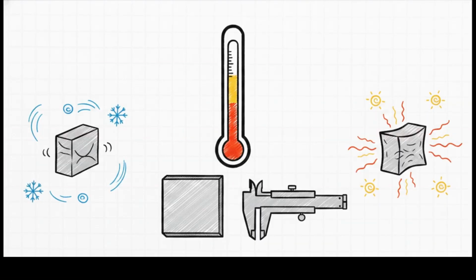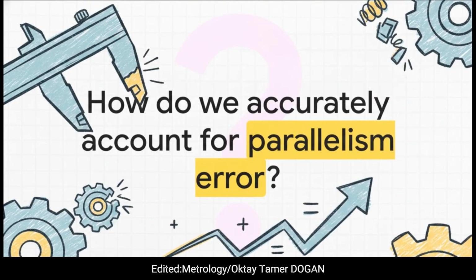Lab environments profoundly impact dimensional calibration. There is a universal consensus that the steel in these devices hits its optimal, most predictable thermal state at exactly 20 degrees Celsius. It's the absolute truth for standards organizations and manufacturers alike. Any deviation from 20 degrees creates quantifiable uncertainty because the material physically expands or contracts. And remember, that thermal error hits both the caliper and those incredibly expensive gauge blocks you're using. Depending on how accurate you need to be, you absolutely cannot ignore this component in your final math. But hey, thermal expansion isn't our only enemy. Mechanical wear over time is another massive headache, which leads us to a pretty critical question.